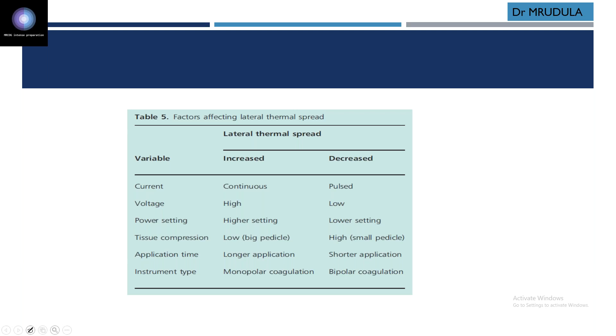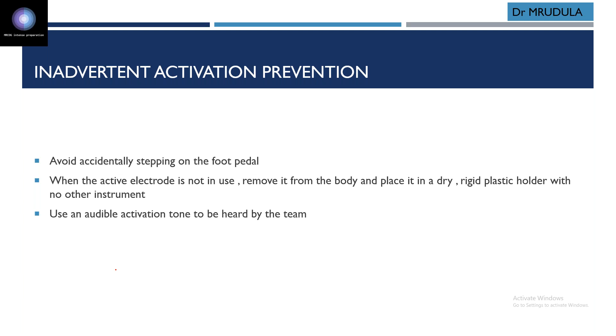Now coming to inadvertent activation. What happens is you are not using that electrode. You have just kept the instrument inactive, and sometimes you just press the pedal or activate that electrode, and it causes a burn to an unintended area where you are not supposed to use electrosurgery. To prevent it, avoid accidentally stepping on the foot pedal. When the active electrode is not used, remove it from the body and place it in a dry rigid plastic holder with no other instrument. Use an audible activation tone to be heard by the team. So when you press the foot pedal, there should be an audible activation tone so that you understand that you have inadvertently pressed the foot pedal.